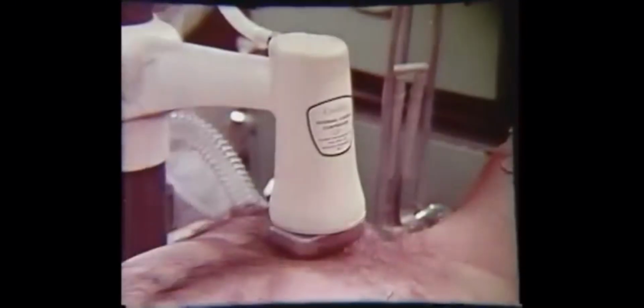The oxygen-powered external cardiac compressor is applied. Confirm that the master valve is on and that the compressor force control knob is turned completely off to the full counterclockwise position. Turn on the compressor switch. Turn the force control knob clockwise to provide approximately 1 1/2 to 2 inches of chest depression for the typical adult. This requires 60 to 90 pounds of pressure. The piston cycles 60 strokes per minute.